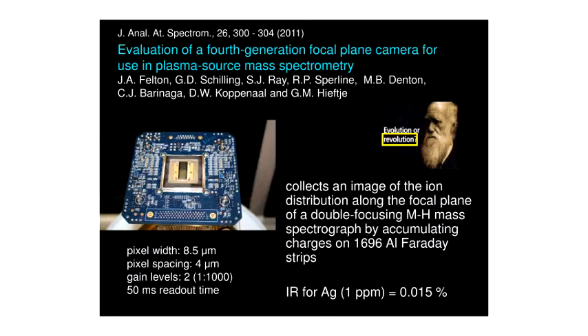It is a series of Faraday detectors in the form of a fine strip of metal — in this case aluminum, in other cases gold. The pixel width of the Faraday detector is only 8.5 micrometers, and they're separated by 4 micrometers. This device is capable of multi-isotope detection when placed in the focal plane.